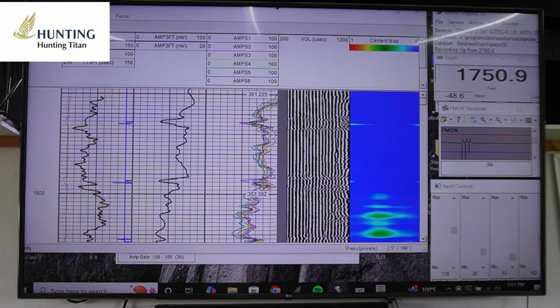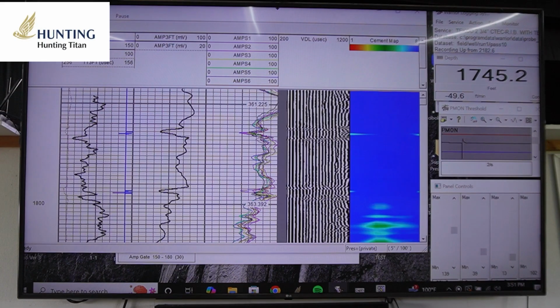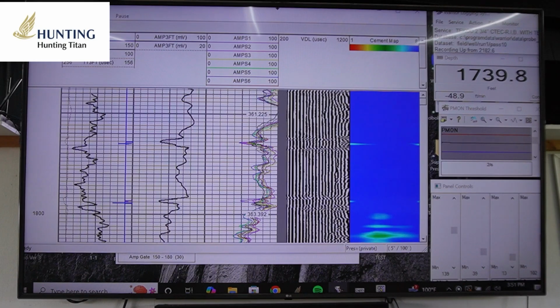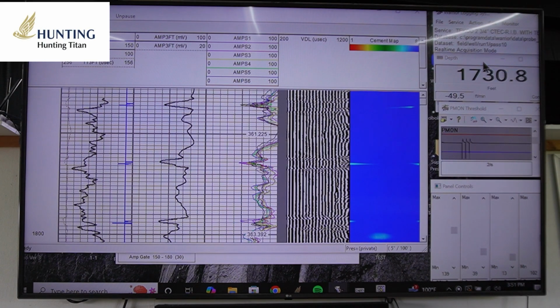We are now into our free pipe. Remember, we set our amplitude to read around 81. Now, you may recognize some of the sectors went off over 100. You see in that one spot, it just rings louder where that can was sitting than where we calibrated with our 3-foot can. So just understand what we're saying. They don't read identical compared to the probe tools. So, okay, what else we have here?